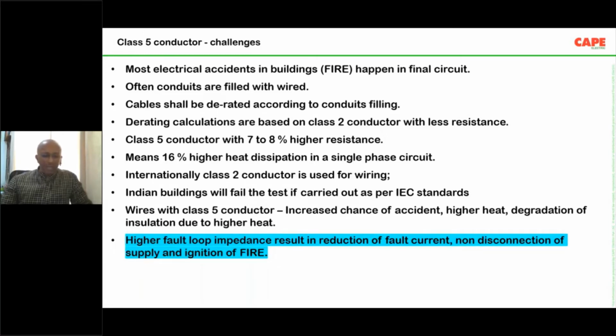If the impedance of the circuit is higher, the fault current is lesser, and most often the protective devices will not trip. Let's say, for example, you have an MCB, but the MCB is not tripping because of the higher impedance of the circuit, and that leads to fire. So non-disconnection of the supply leads to fire due to short circuit.